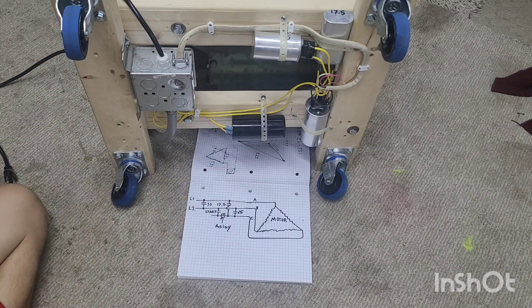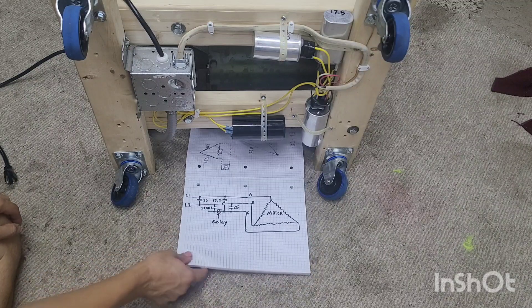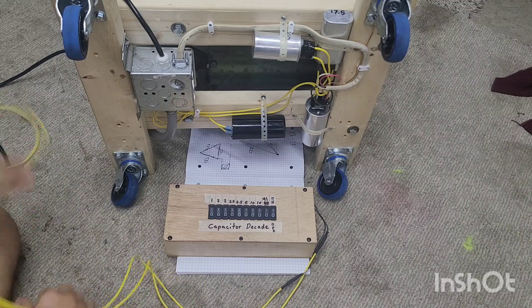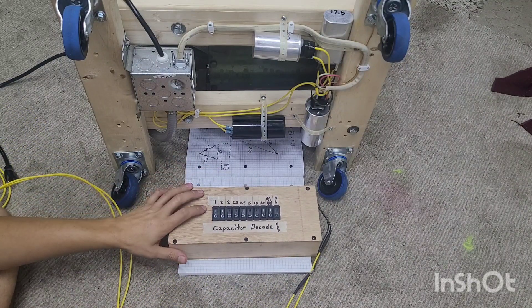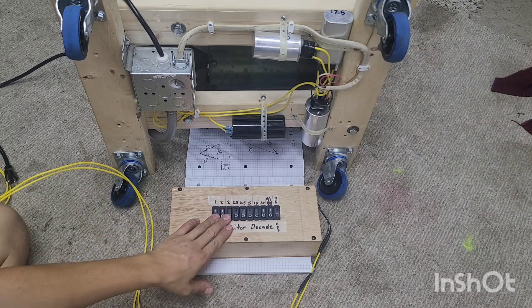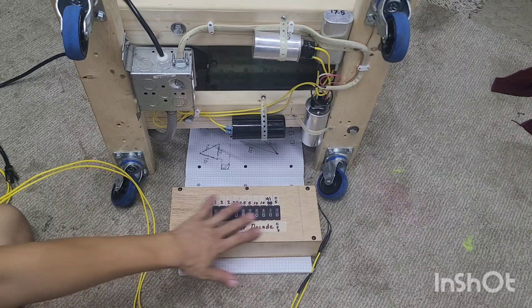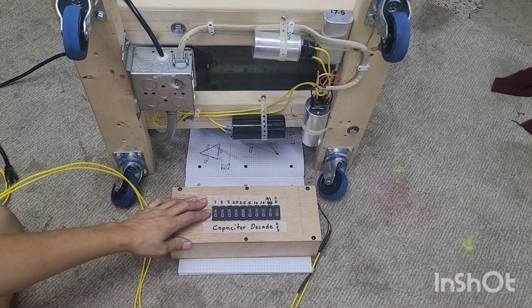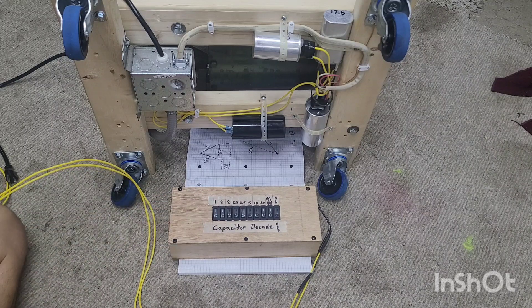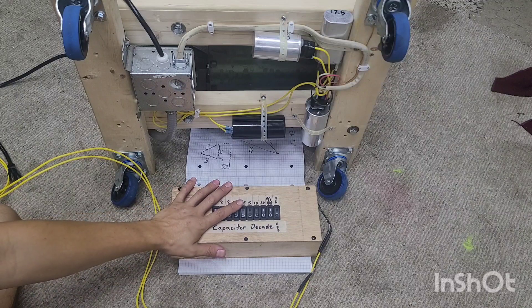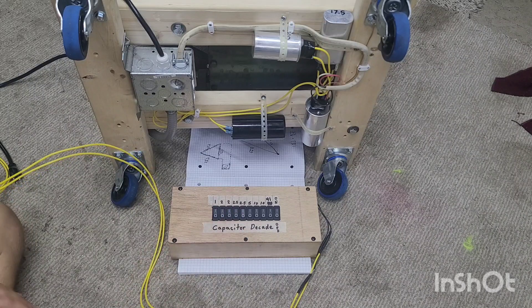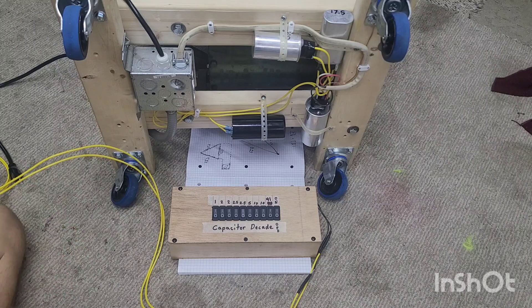Through some testing, this is what got me the balanced phase voltages. To get this, I had to use a couple tools. One was this homemade tool. This is a box that has a bunch of capacitors in it of different values. They call these a decade box. You can switch these on and off, and I can use this to make any variety of capacitance value from one to somewhere in the 70 something microfarad range. I was able to use this with a voltmeter hooked up.